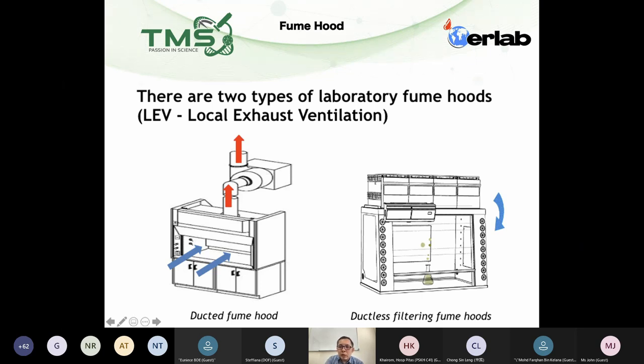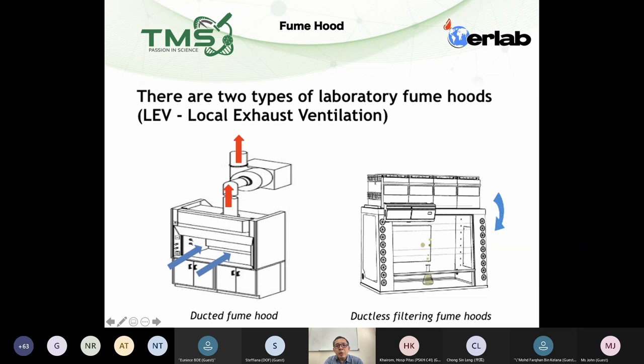There are actually two options of fume hoods: ducted and ductless fume hoods. The ducted fume hood is basically called the LEV — Local Exhaust Ventilation — because DOSH specifies it should have five components: the hood, the duct, the air cleaner, the fan, and the stack, which is the chimney.